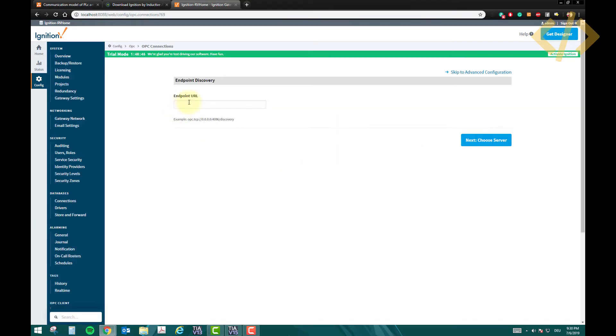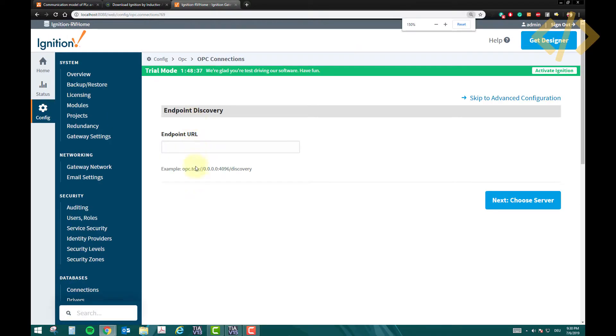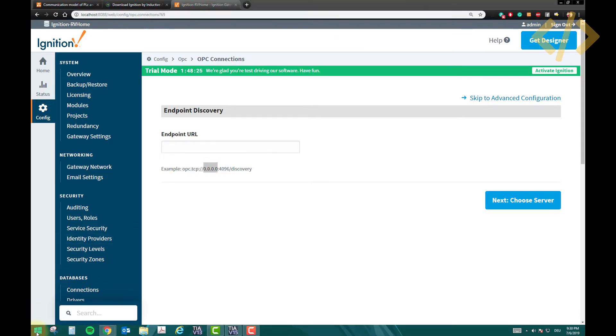And then it is asking for endpoint URL. Now this is the endpoint which you have to define here. So here they say example is OPC, if you can read it, opc.tcp 0.0.0.0:4096/discovery. Now what you can do is you can define this endpoint URL, and this instead of 0.0.0.0, it should be your ethernet card address.